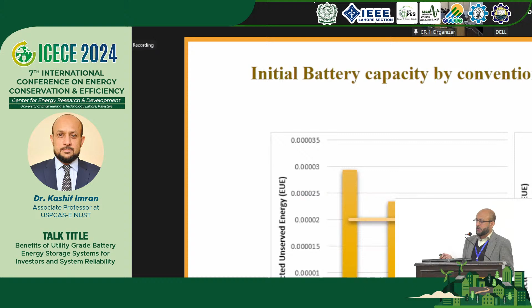Using the Monte Carlo simulation method for calculating reliability indices in MATLAB using available code, we determined a number of reliability indices, for example, expected unserved energy. In the case of expected unserved energy, you can see that if we start increasing the battery capacity from 25 megawatt hour to 50, to 100 and so on, then there comes a point where we are able to meet the threshold level defined in grid codes, for example.